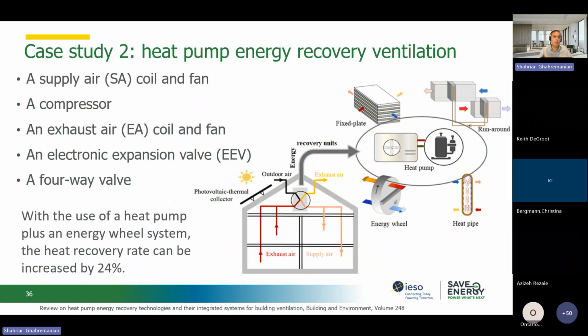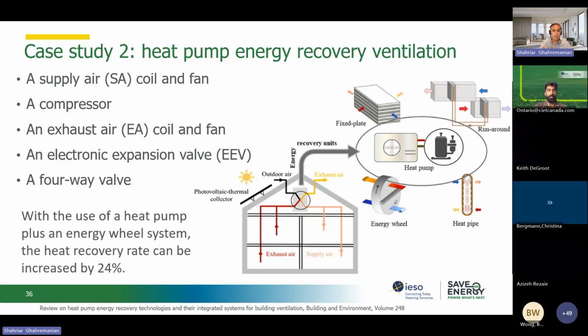The second case study that I have is the heat pump combined with an energy recovery ventilator. So basically, typically we put in an energy recovery ventilator, and then we mix that air and send it back. But in this case, instead of doing that, let's send that air to a heat pump, either from a heat pipe, energy wheel, fixed plate, or run-around coils, whatever we have, and let the heat pump take that and convert it to what we want.